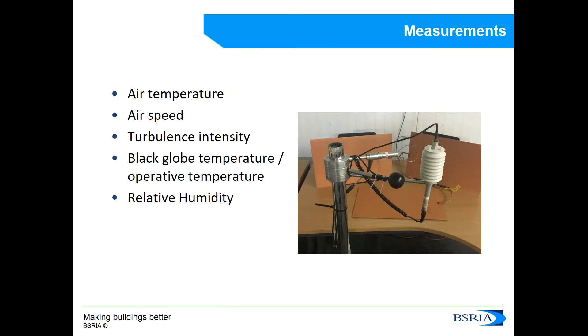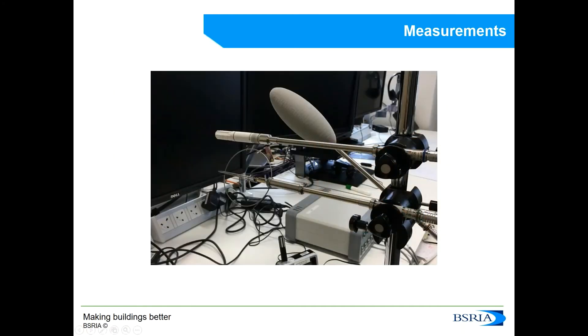To measure thermal comfort involves a little bit more than measuring the temperature and humidity, although these are two parameters that we have to measure. The other parameters that we have to measure are the airspeed, the turbulence intensity, and the globe temperature, as you can see here using a black globe. Or if you're not measuring the black globe temperature, you can measure the operative temperature using a sensor that looks like a microphone, and you can still obtain the thermal comfort indices. What you can see here in white is the humidity sensor, and there is also an anemometer with a metal shield to protect it, which measures the air temperature and airspeed as well.